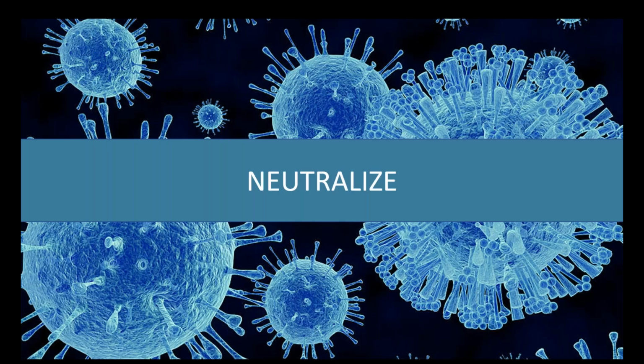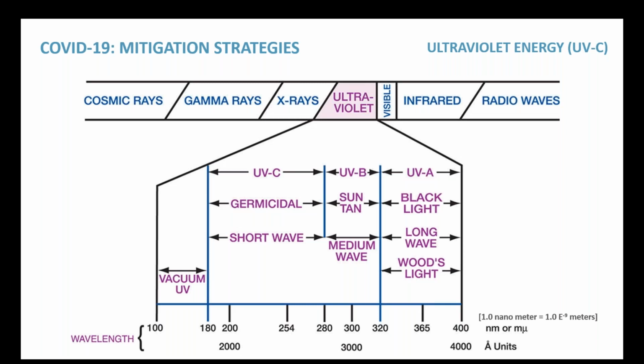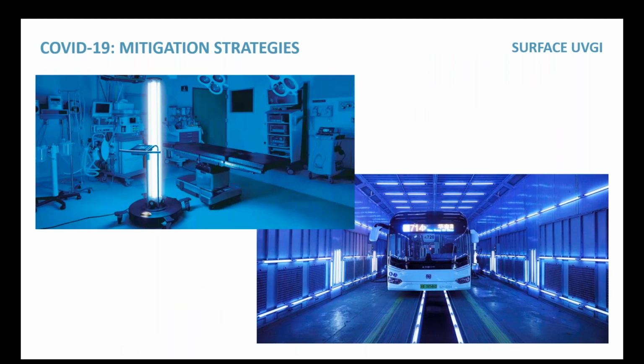So now let's move on to sort of neutralization strategies. We discussed a lot about neutralization strategies previously. The first one I'll start with is UV, ultraviolet energy. This one has been around for quite some time. There is a decent amount of scientific data available for the effectiveness of UV systems. ASHRAE notes that these systems can be applied both in addition to mechanical filtration or potentially in scenarios where you're unable to do mechanical filtration. And essentially what these UVC systems are doing is targeting a specific wavelength that has been shown to be effective at neutralizing viruses, bacteria, and certain things that are in the air.